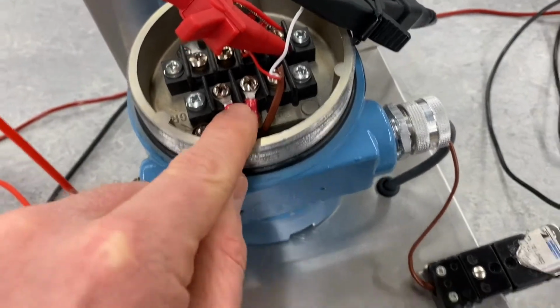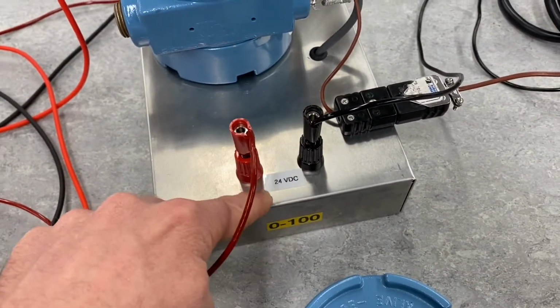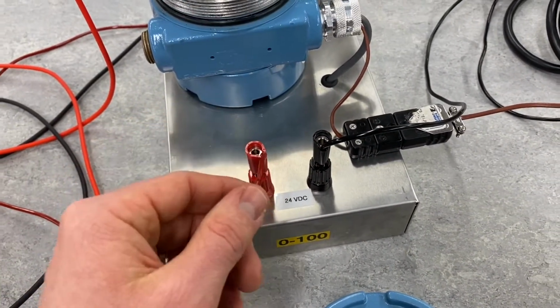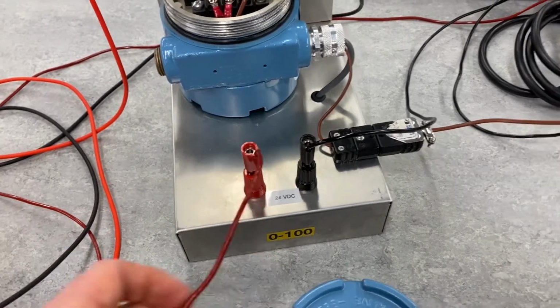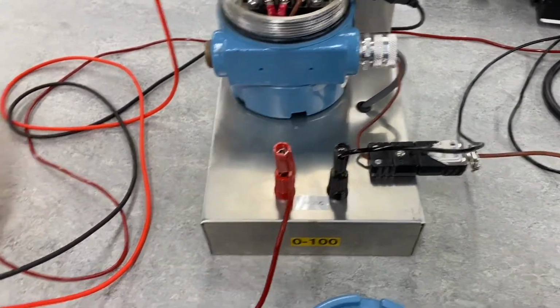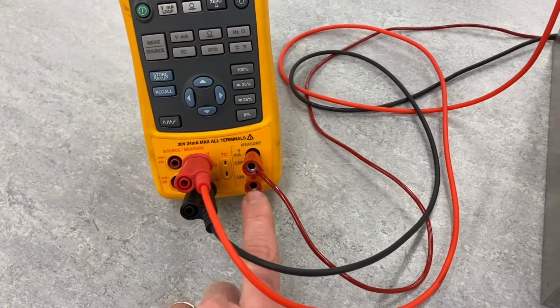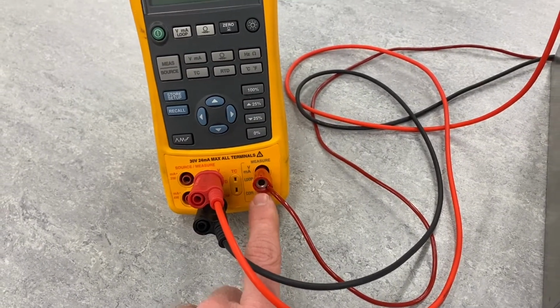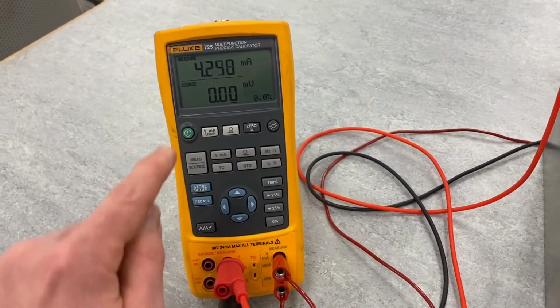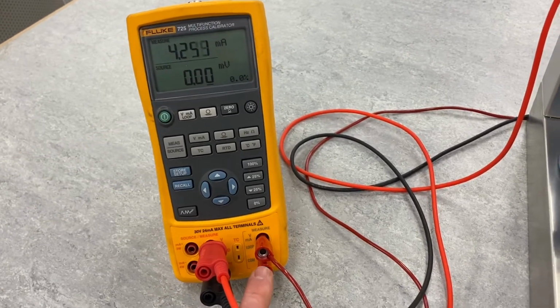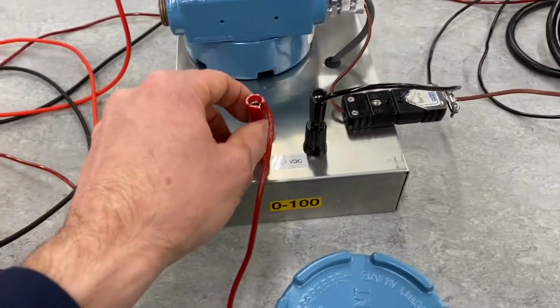The output here, which is these two terminals right here, is broken out down here on this board for quick connect. This is where we're going to be connecting our 24 volt source, and we're also going to be connecting the milliamp side of our calibrator, so we can read a milliamp value from our transmitter in series.